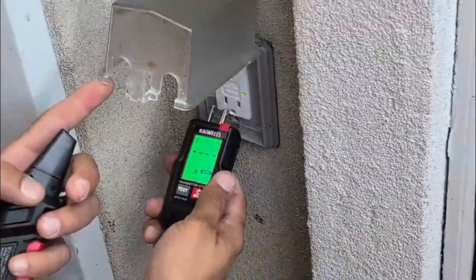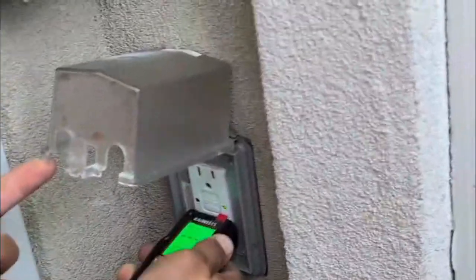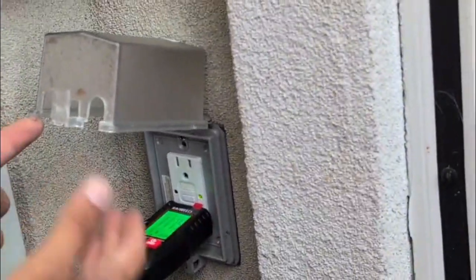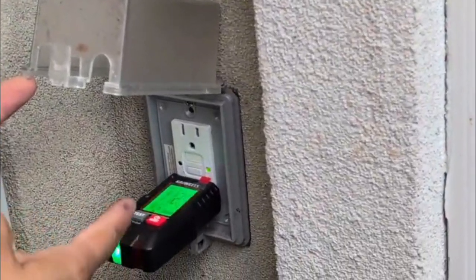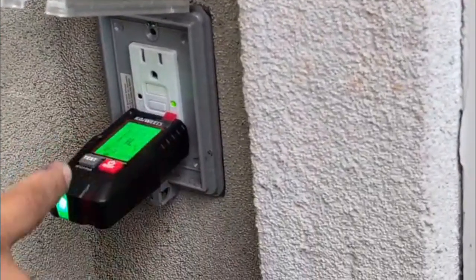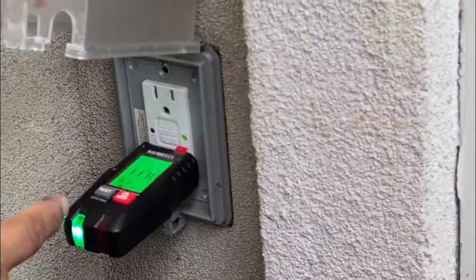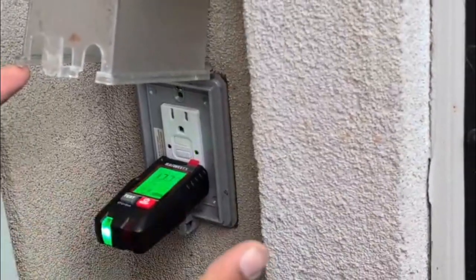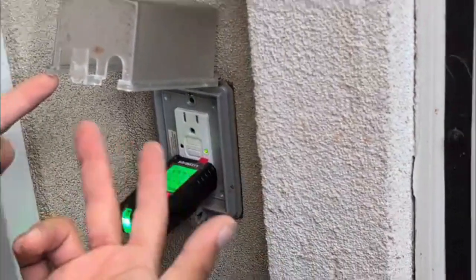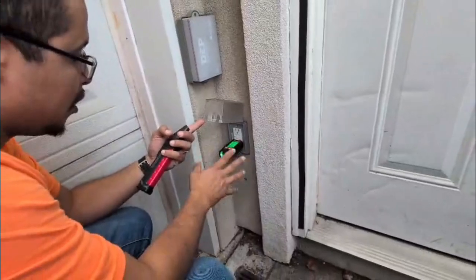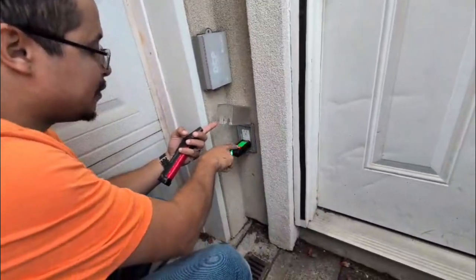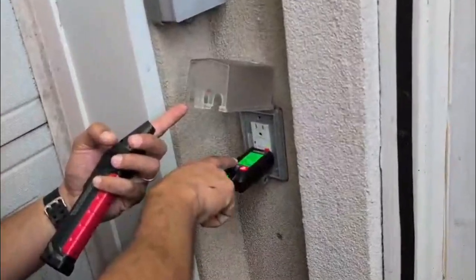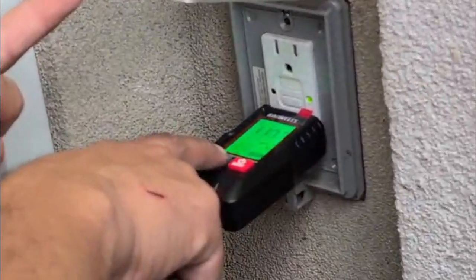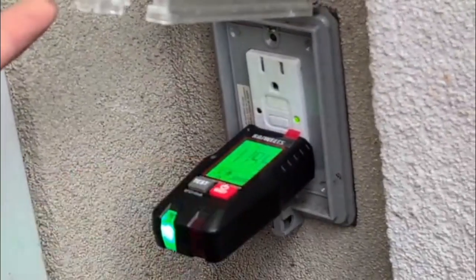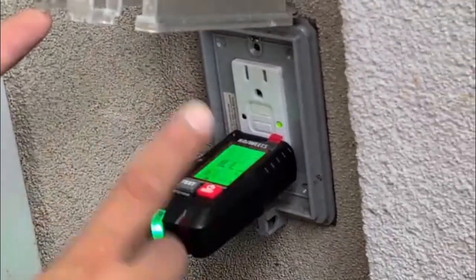So now we're going to plug it in. And as you can see, it's going to take some voltage reading. You can see the voltage is bouncing around. And there you go, steady voltage at 119, 122, that's nominal, that's normal voltage. 123, 121, okay cool. And then it even tells you if the wiring is correct, so you got your neutral, your line, and your equipment ground, and it tells you if it's correct voltage, which is pretty good.